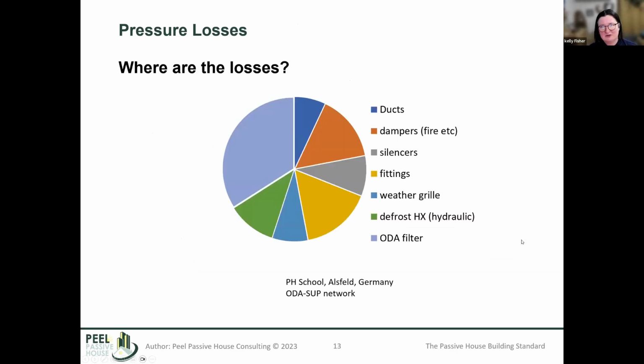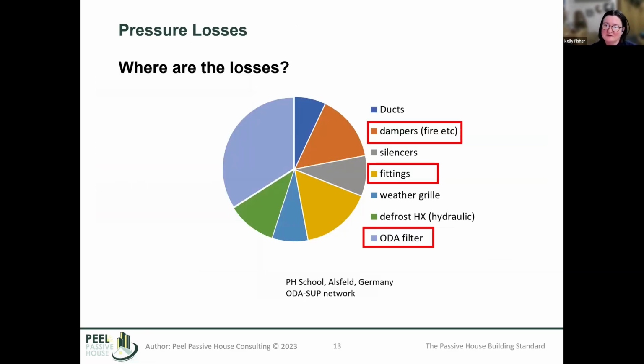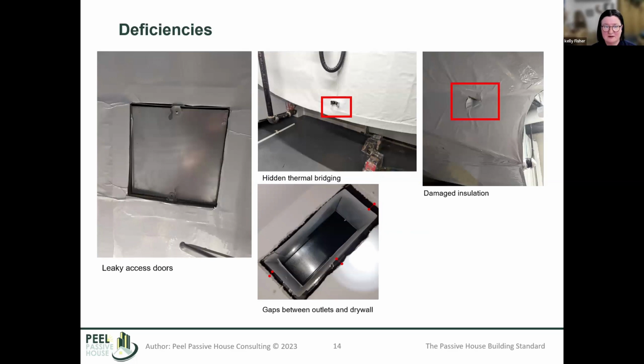So when we're talking about pressure losses in general, we find that a lot of our losses come from dampers, fittings, and filters. So being mindful of making sure that those are included in design, and properly sealed so that adjacent ductwork is not affected, is really, really important, so that you don't exceed what your machine can provide to you.